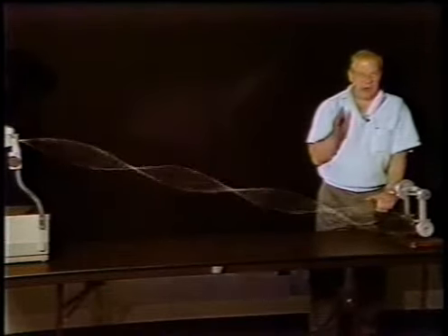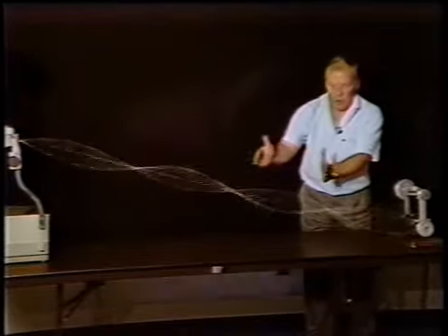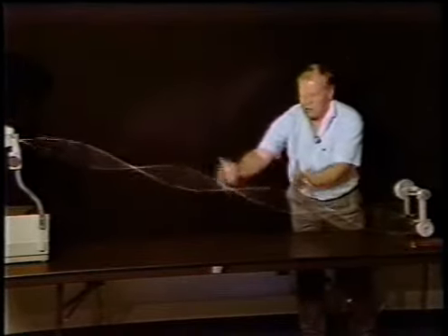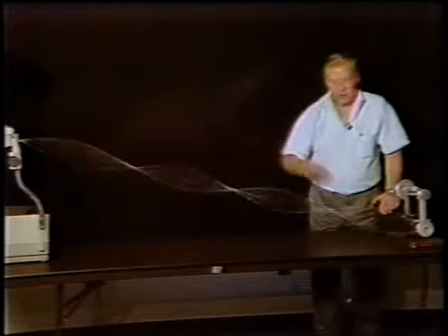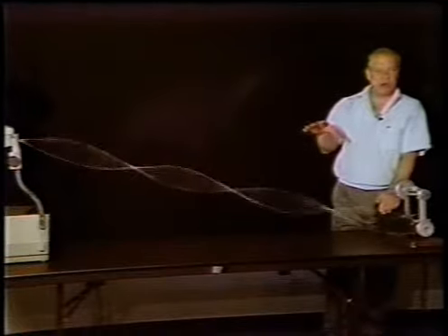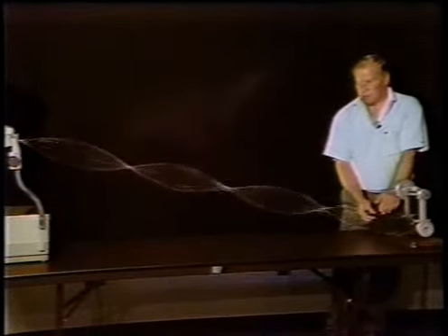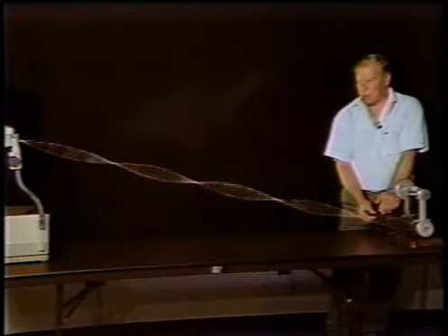When you install your piping and the support hangers, what would be preferable is to space your supports at non-uniform distances, perhaps 13 feet, 9 feet, 11 feet, and so forth, so you avoid the possibility of sending that piping into a standing resonant mode similar to what we're demonstrating here. There's the fourth bending mode, continuing to bring it on up in speed.